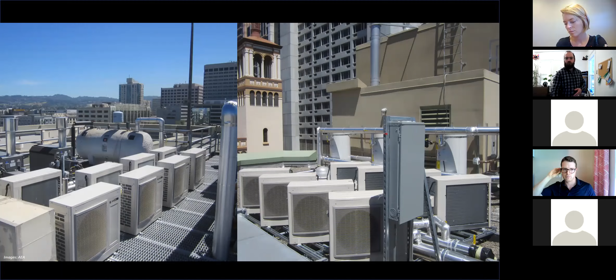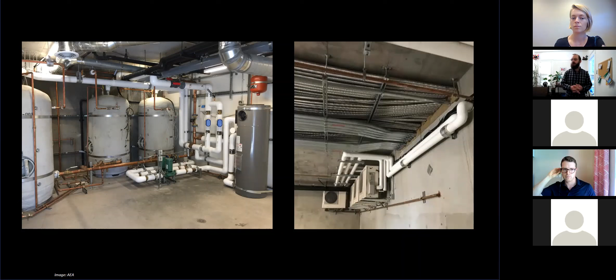This is a similarly configured system by Sanden, but trading off fewer compressors for considerably more hot water storage. There are a lot of ways you can slice and dice and design these things, and there are trade-offs between more storage and more compressor capacity and electrical needs. These are things you'll want to take into consideration. On projects of this size, you'll typically have an engineer involved, but make sure you're talking through different permutations.